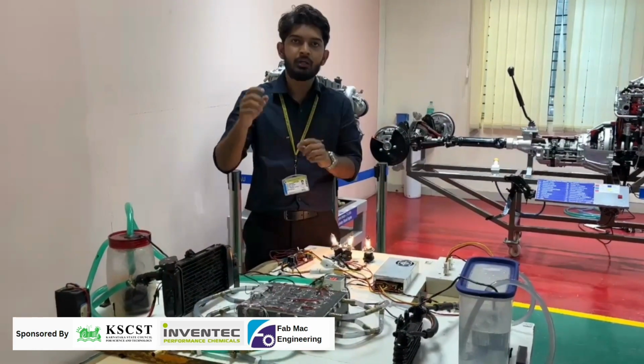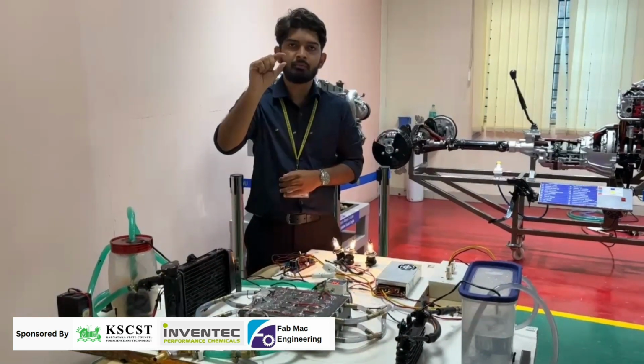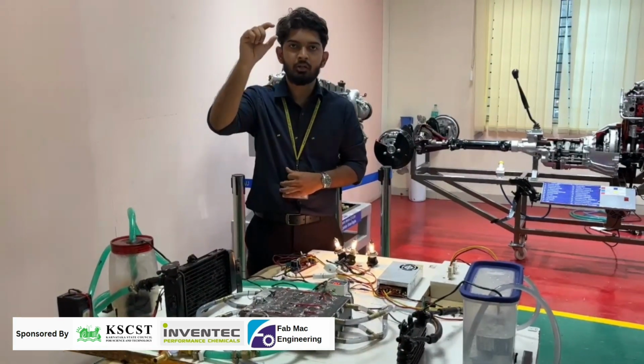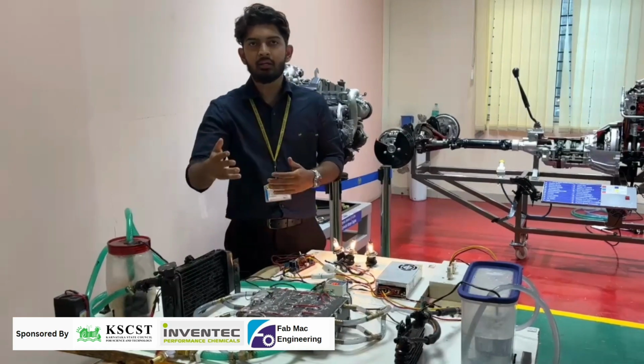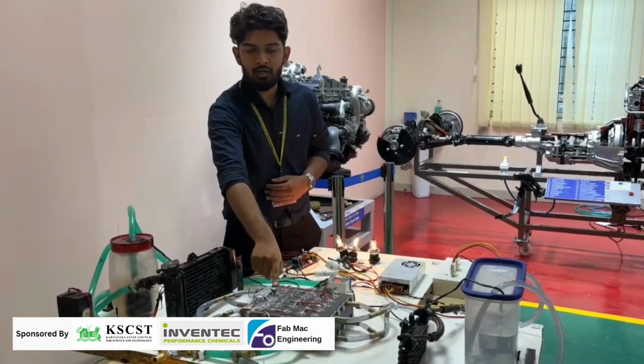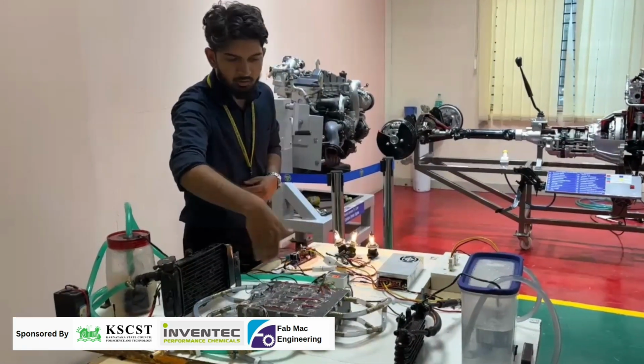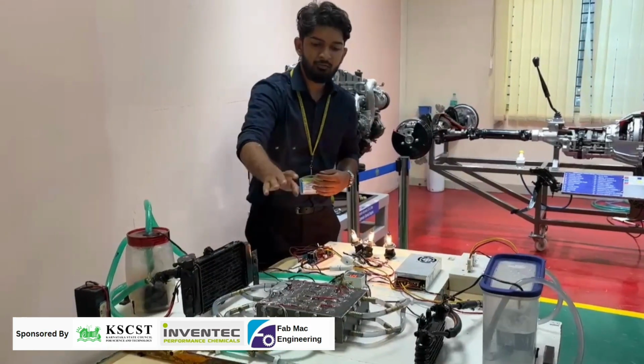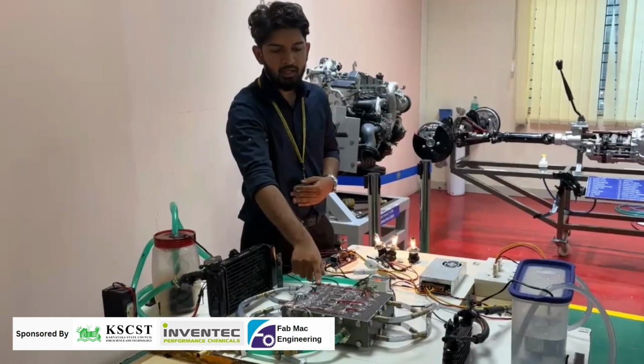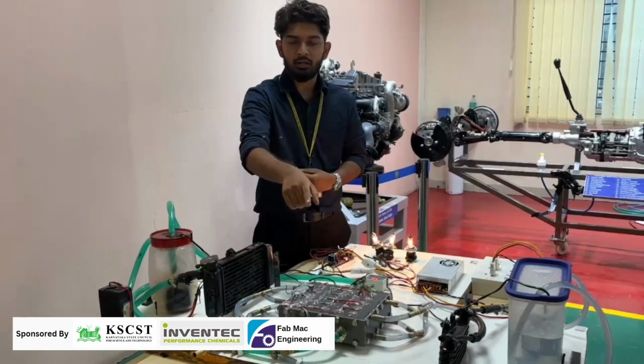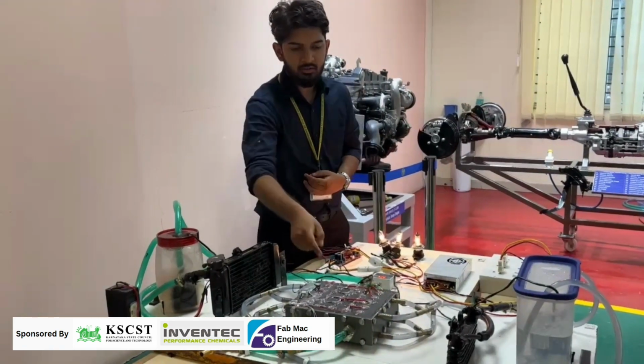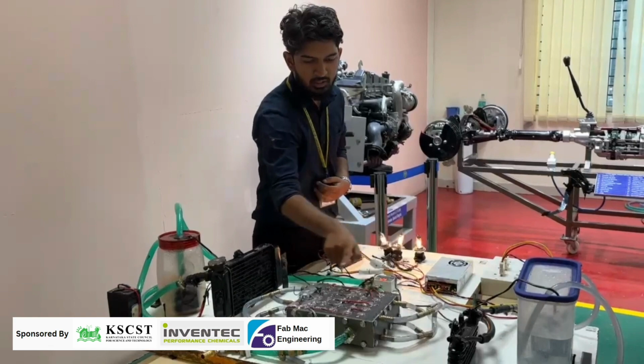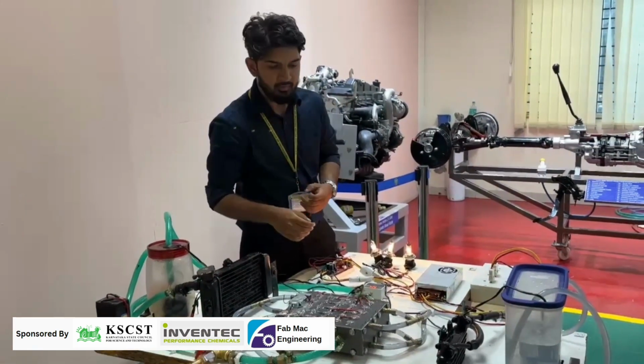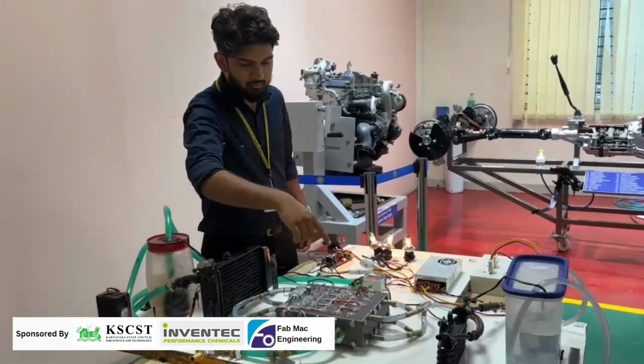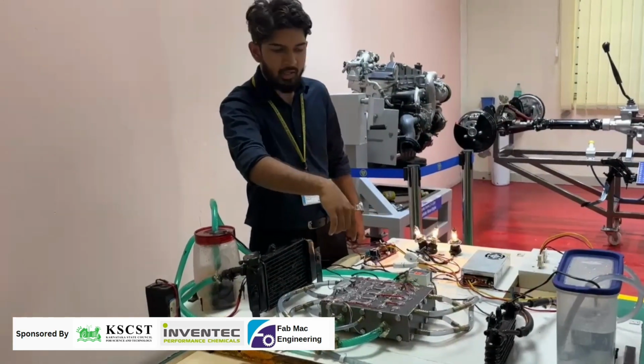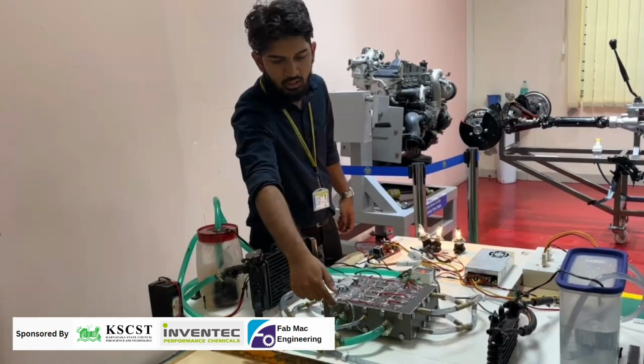The tap cooling uses cooling plates which are 12 mm thick at the top and bottom, and to make an enclosure we have 2 mm aluminum plates enclosing the battery pack all around. First, holes for the batteries were drilled on the 12 mm plate, then through-holes were drilled lengthwise for the coolant channels. We also drilled holes along the perimeter of the battery pack and threaded them to attach fasteners.